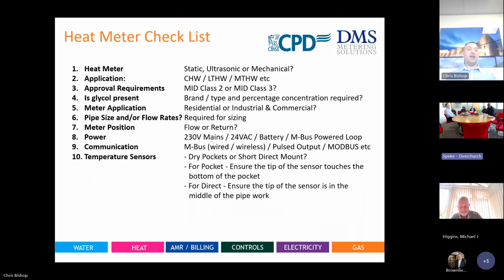And then, yeah, just our basic checklist. But heat meter, what do we select? Static: you might have glycol in the system, or the client might have a large heat pump network. Yeah, we would select that. Ultrasonics might be heating and cooling, with no glycol involved. If you want something quick off the shelf, anything like that, ultrasonics would be an option.